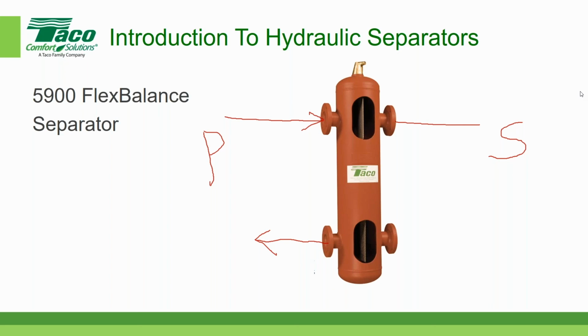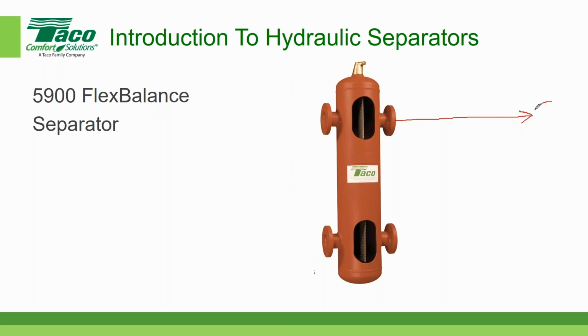I kind of screwed that up, put the S in the wrong direction. But anyway, that's going to eventually be connected to a pump. So you have to look at the requirements of the pump and also the requirements of the hydraulic separator. In general, this distance from here to the suction side of the pump wants to be somewhere between 5 to 10 pipe diameters.